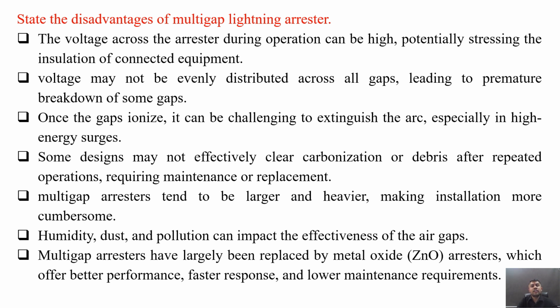Some designs may not effectively clear carbonization or debris after repeated operations, requiring maintenance or replacement. Multi-gap arrestors tend to be larger and heavier, making installation more cumbersome. Humidity, dust, and pollution can impact the performance of these air gaps or lightning arrestors. Multi-gap arrestors have largely been replaced by metal oxide arrestors, which offer better performance, faster response, and lower maintenance requirements. So these are several disadvantages of multi-gap lightning arrestor.